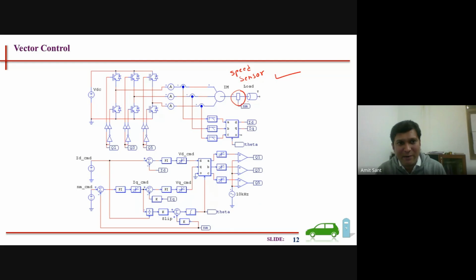Yes, if the speed sensor fails, that means the output is 0. Then my control system will think the speed is 0, and increase the torque and current so that higher speed is attained. But the speed is not actually 0 -- it has some speed, so it may result in an accident. So the alternative is that if the speed sensor is not working properly, I should get a signal and the gate pulses should be stopped so the motor cannot move. But if the vehicle stops suddenly in the middle of the road, it may also cause an accident. So instead it should give a signal to the driver -- a beep or buzzer sound -- so the driver knows there is a fault and needs to stop the vehicle. He can then give some signal and stop it.